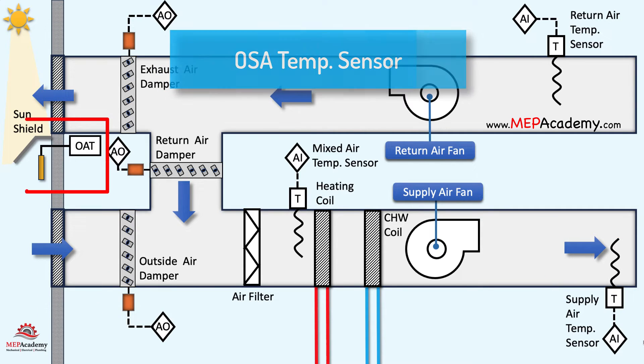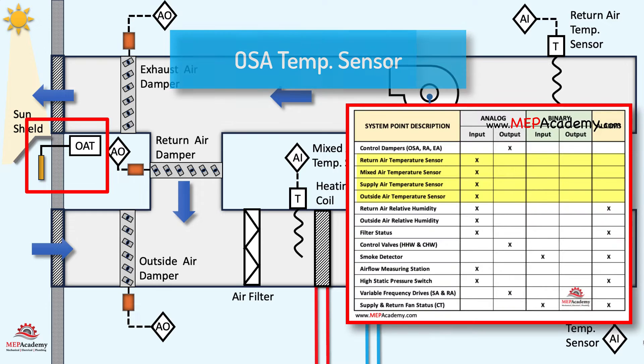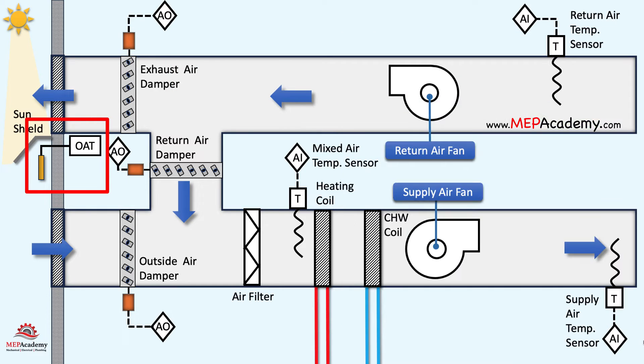The outside air temperature sensor is crucial for the control of economizer systems and air handlers. Economizers utilize outdoor air for cooling when the outdoor conditions are favorable. The sensor helps determine whether the outdoor air is suitable for free cooling, allowing the system to reduce reliance on mechanical cooling and improve energy efficiency.